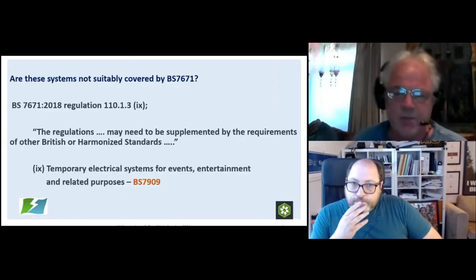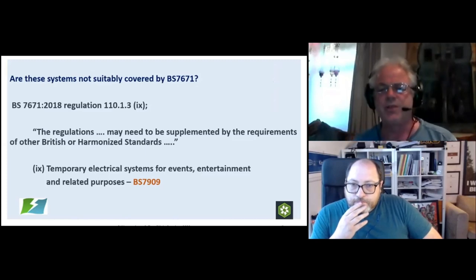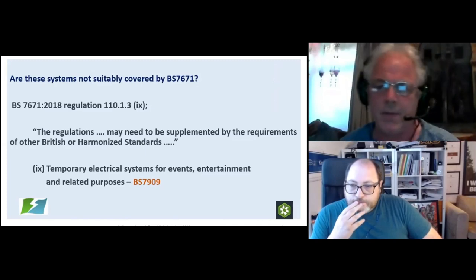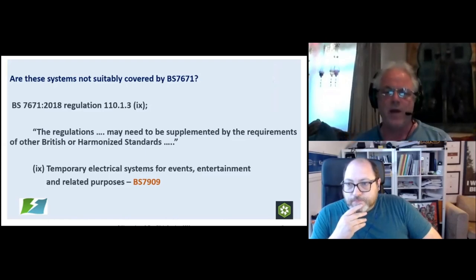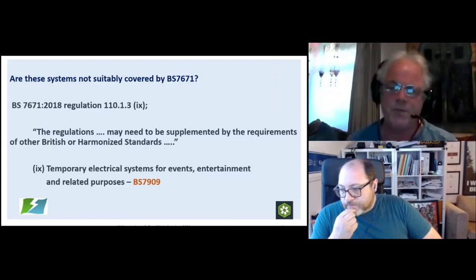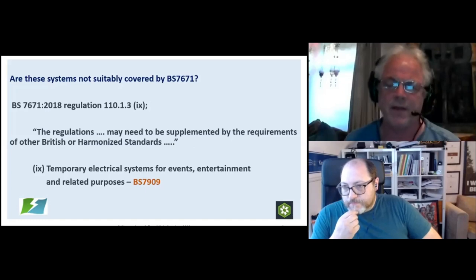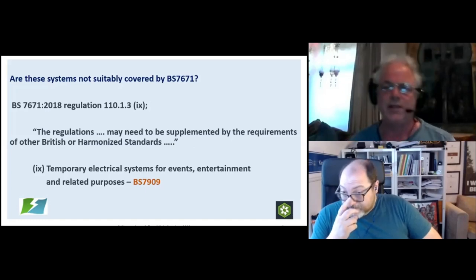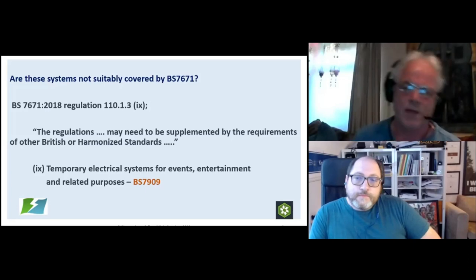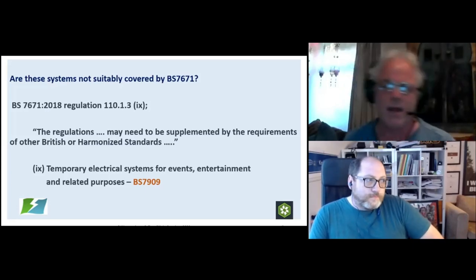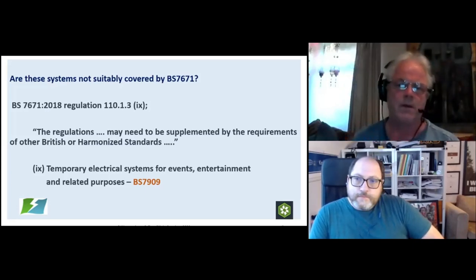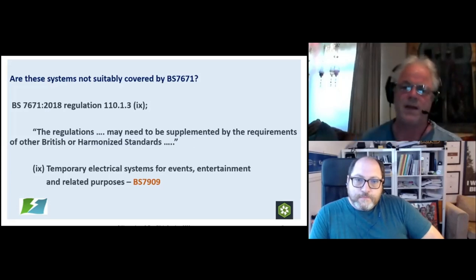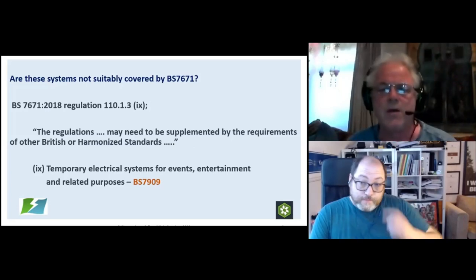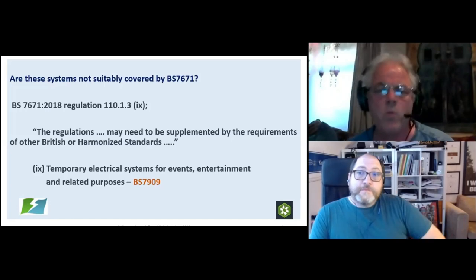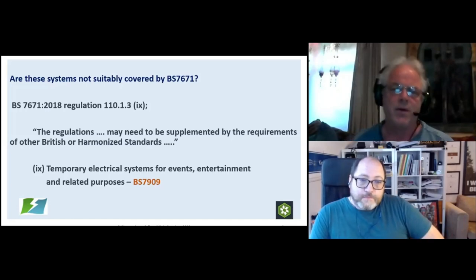So are these systems not suitably covered by BS7671? Well, obviously, it's an electrical system and it has to be applicable to BS7671 in many ways. We use BS7671 when we're looking at things like automatic disconnection, RCD protection, types of cables, cable runs, switchgear. There are so many issues that come up, like calculating maximum demand, calculating load current, earthing and bonding, all covered to an extent by BS7671.